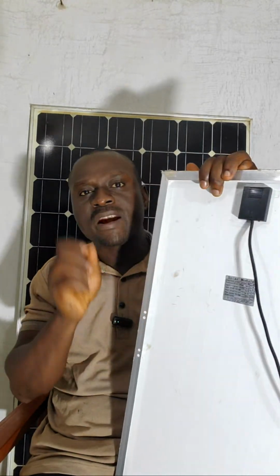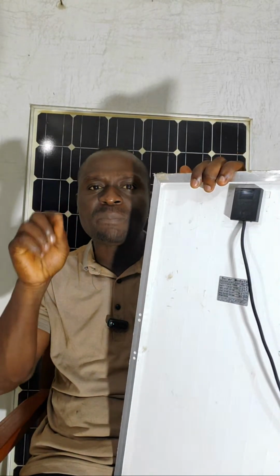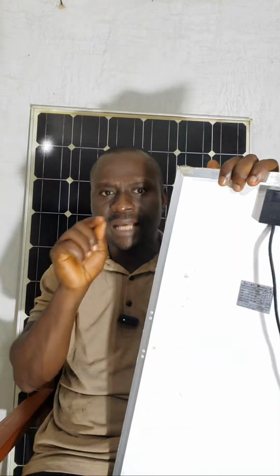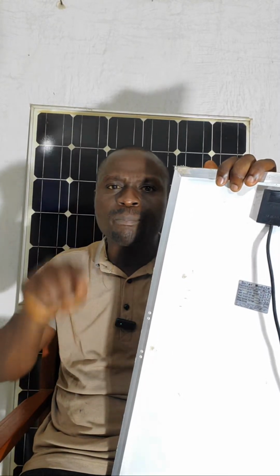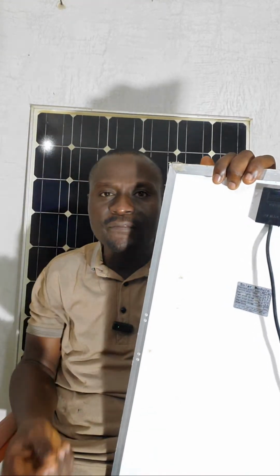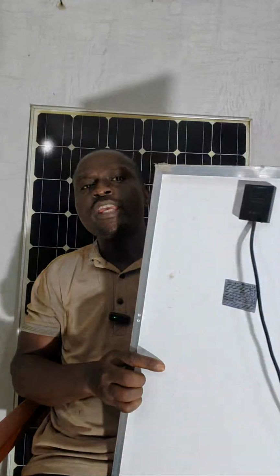Now, this VOC is very important when you are sizing an MPPT charge controller. For an MPPT charge controller, you will always see a specification written there that the maximum PV input voltage of this charge controller is 150 VDC, 250 VDC, 195 VDC, or 450 VDC, 500 VDC.